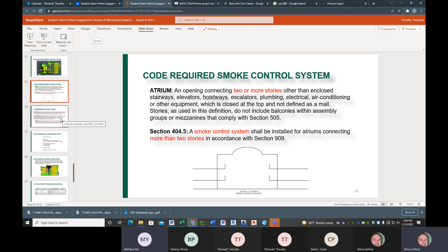If we go to the next slide, this is basically the code requirements saying that for the situation where you have the atrium, the code says you need to use the exhaust method for the atrium as a smoke control system. And the criteria that the smoke control system is designed to is to maintain a tenable condition for occupants to evacuate. Section 909.8.1 says that the height of the lowest surface of the smoke layer shall be maintained not less than 6 feet above the working surface. So meaning that we need to maintain tenability condition 6 feet above the working surfaces. So that's the benchmark for our design.